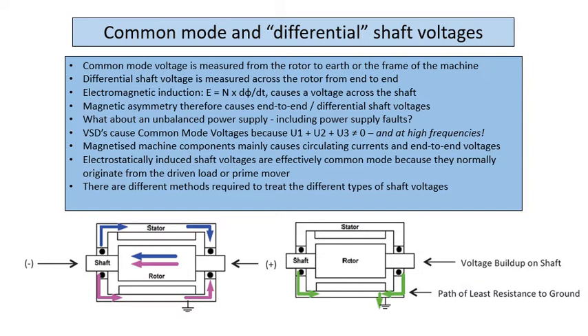However, if your U1 plus U2 plus U3 does not equal 0, then your capacitive coupling between the winding and the stator core causes the stator core to adopt the neutral point voltage, i.e. the common mode voltage. And that's how you get it both in the VSD form and in direct online or power frequency form.